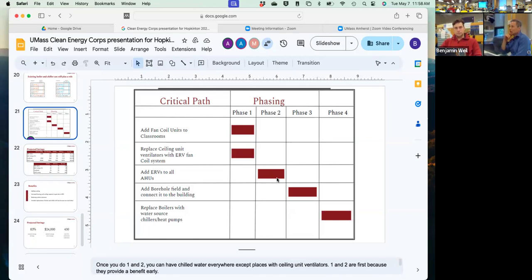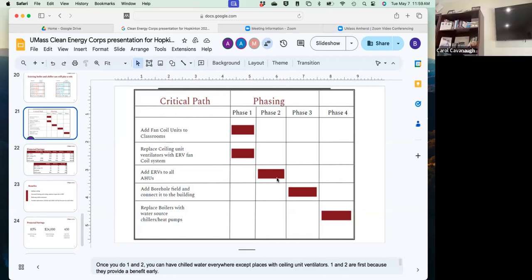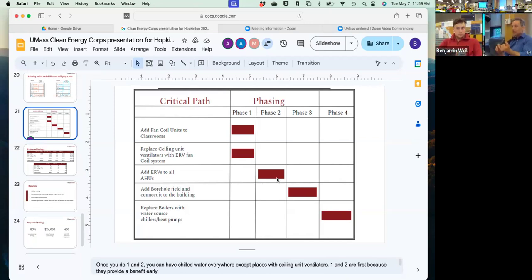So yeah, if you are confident that systems are actually running down, that it's not just a matter of replacing a drive or a motor, like if you've got enough components that are failing, or if you've got leaks in your coils, right? Any of those things where enough components start to fail, then you really do want to say, well, you know what, let's just replace the whole thing. But if basically your drives are working fine, your motors are high efficiency motors and don't need replacement, coils have been in good condition.